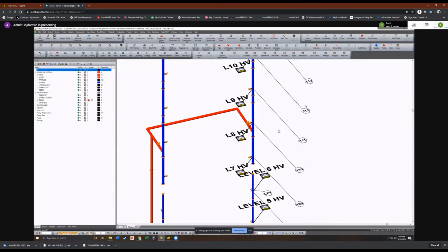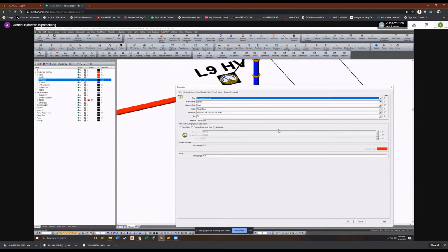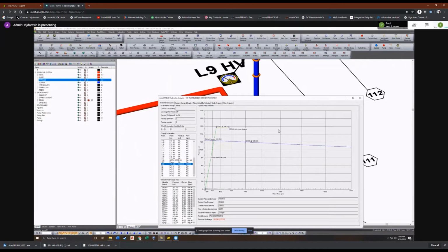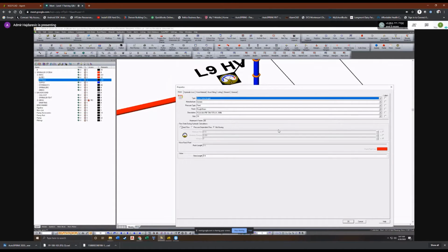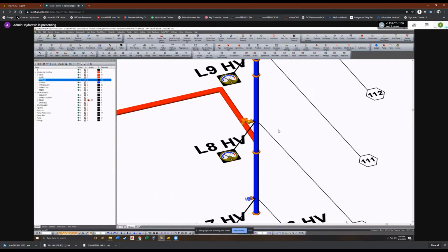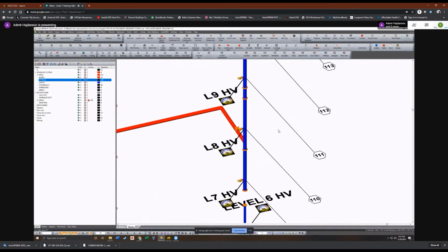Okay, so you're selecting the supply information, so it's going to show graph information here. Let's go down to the checkpoint gauge data below. So there we go. Level 7 hose valve, we are getting 0.01 GPM, 220 PSI. Okay, that seems accurate. Now, I'm just curious, if we turn that hose valve back off, that L7 HV is not going to populate anything. I want to double check this to make sure. Didn't last time, I don't think. Let's see. Yeah, okay, it's all zeroed out. So unfortunately we have to tell the program to flow water there, even just a tiny amount of water, to be able to populate and generate pressure data at that location. Well, that helps.